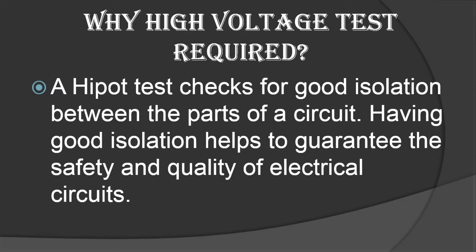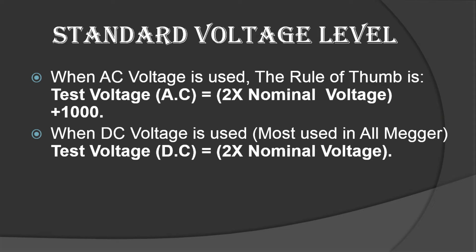What are the standard voltage levels when checking the insulation withstand capability? You have to apply voltage based on these rules. For AC voltage: AC voltage = 2 × nominal voltage + 1000 volts. The nominal voltage is the voltage specified for the cable. For DC voltage: DC voltage = 2 × nominal voltage — no extra 1000 volts is added for DC. This is the standard voltage used to check the withstand capability of the cable.